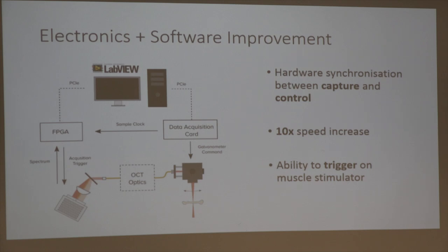Another advantage, which I'll show you later, is hardware synchronization. Although both the galvanometer, which steers the beam around the sample, and the line scan camera, which captures the signal, are both connected to a PC, the FPGA is synchronized with the data acquisition card and hardware that triggers and drives the galvanometer. The nice thing is that because everything is at the hardware level, they're completely synchronized.